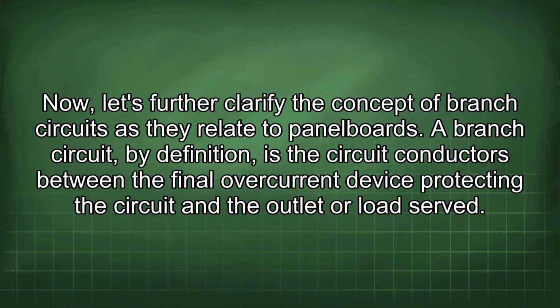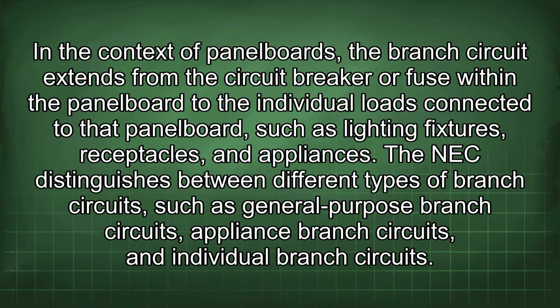Now let's further clarify the concept of branch circuits as they relate to panel boards. A branch circuit, by definition, is the circuit conductors between the final overcurrent device protecting the circuit and the outlet or load served. In the context of panel boards, the branch circuit extends from the circuit breaker or fuse within the panel board to the individual loads connected to that panel board, such as lighting fixtures, receptacles, and appliances.